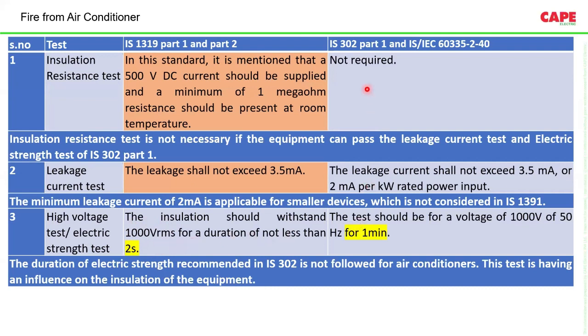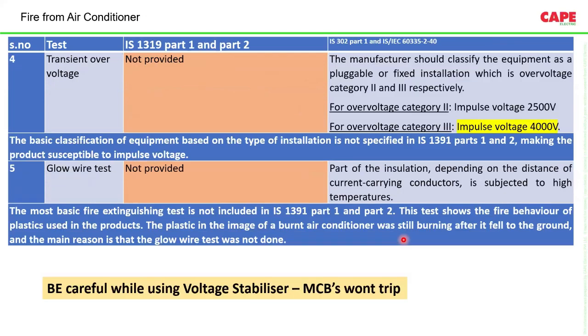But in reality, the duration shown, 2 seconds, is quite short. In practice, the test is supposed to be made for 1 minute. IS 302 recommends making this test for 1 minute. So with an ISI marked air conditioner, you can be sure that the 1,000-volt 2-second test is made, but you should also check IS 302, whether the air conditioner is tested with a continuous voltage for 1 minute. Say, for example, transient overvoltage.